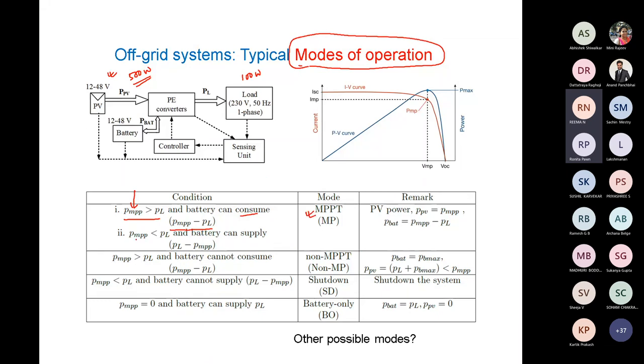Another case: PV power is less than load demand, so the battery has to supply this additional load demand. Let's say the battery has enough charge, no problem, so we'll operate in MPPT mode, using the MPPT algorithm to operate my solar at this particular point. I'm happy, no problem.